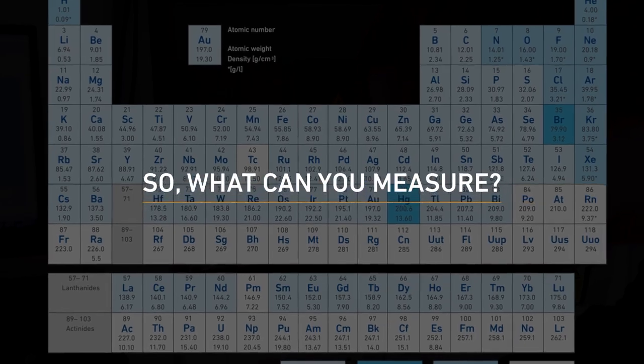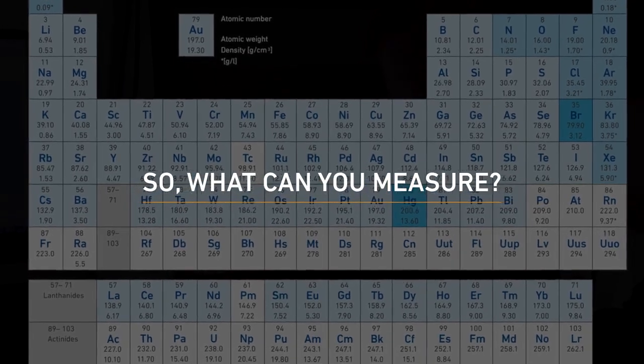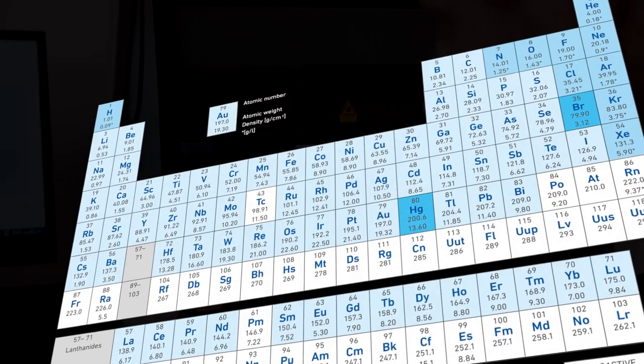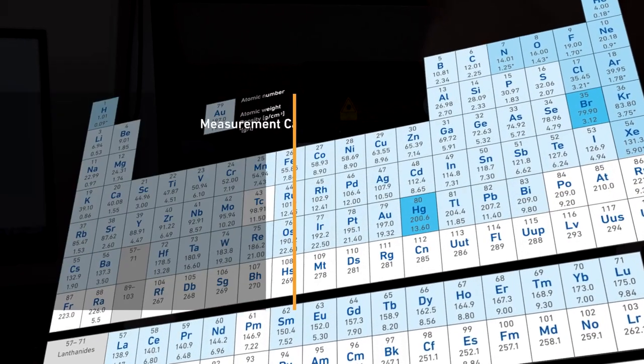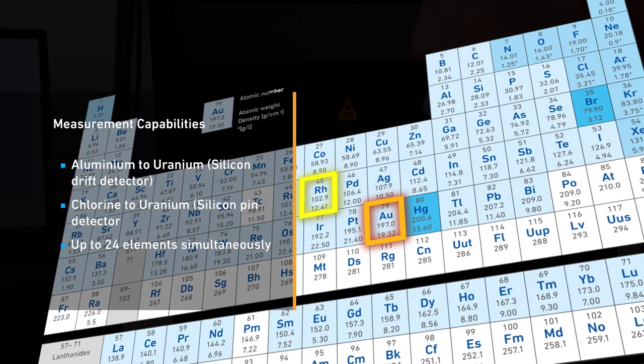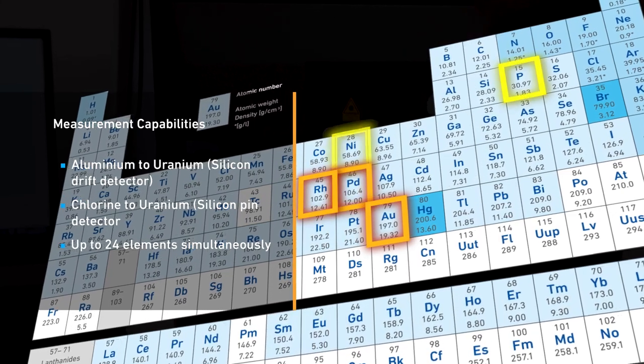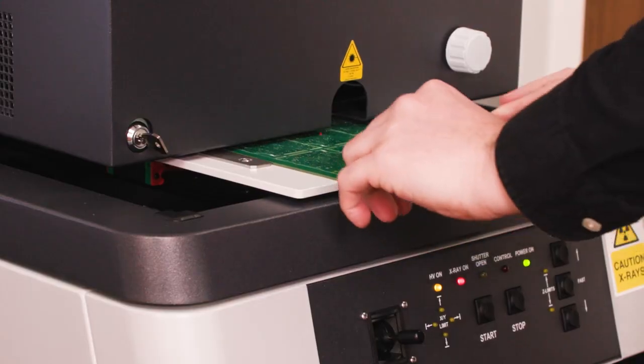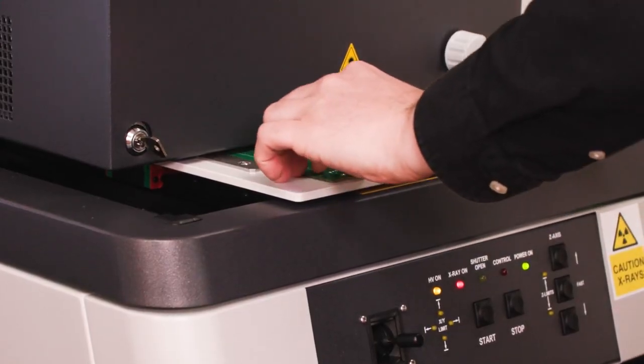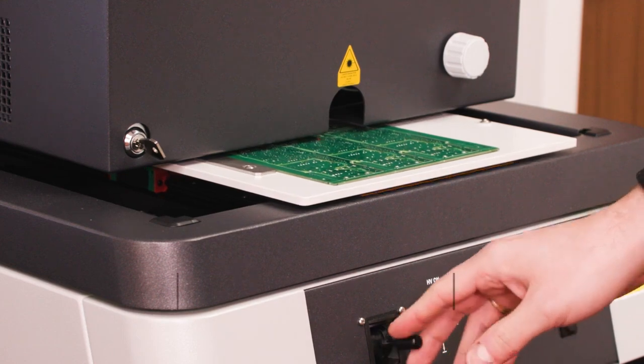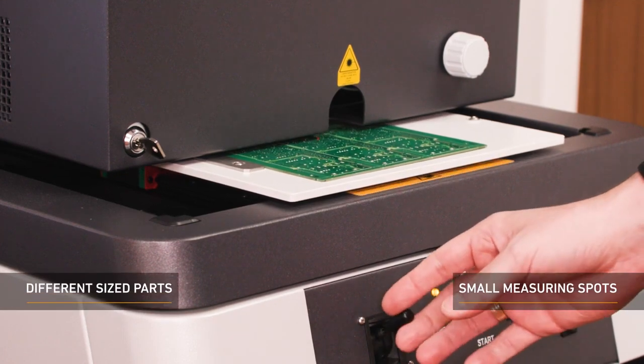So, what can you measure? You can measure a wide range of elements, from aluminium to uranium, including gold, rhodium, palladium and nickel phosphorus. With this instrument, the measuring diameter possible can be as small as 0.1 mm.